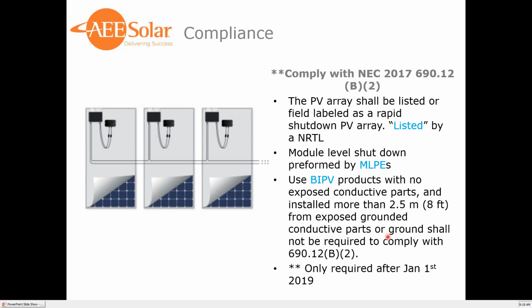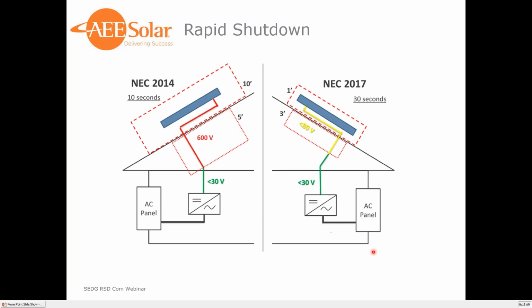Just a side note, the module level was not required until January 1st, 2019. So here's a quick comparison against NEC 2014 and 2017. Initially, the NEC 2014 code was a 10-second shutdown to 30 volts or less, and a TIA was submitted to relax that to 30 seconds. So with the NEC 2014, you have a 10-foot array perimeter and 5-foot penetration into the building where it could be 600 volts. And then the controlled conductors had to reach 30 volts in 30 seconds after the TIA was submitted.